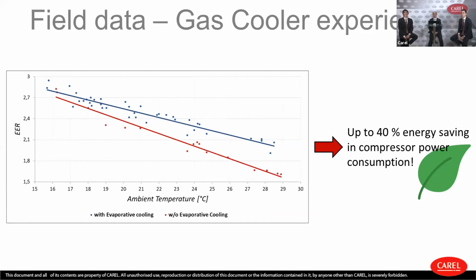So these are the field data. This is a gas cooler experience, a gas cooler installed in Italy where we tried to install the evaporative cooling system. Here you see in red without the evaporative cooling system, and in blue with the evaporative cooling system. On the y-axis you have the index of efficiency.